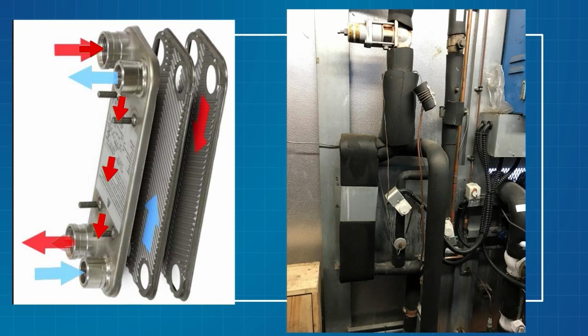We're gonna flow in what we want to chill, and it's gonna come out chilled. It is the heat that we're absorbing with the primary side. Let's think of this as a refrigerated case, right? The primary side is my evaporator, the secondary side is my air, my fan. If I unplug my fan, what's gonna happen to my evaporator? It'll ice up. What's going on with the refrigerant inside? It's not boiling off, I'm flooding. That's gonna happen here.